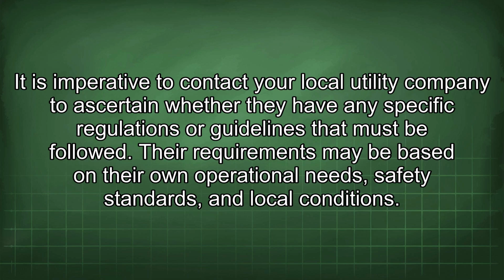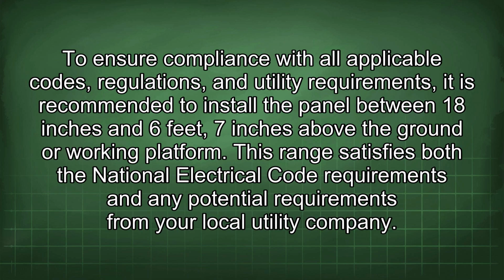It is imperative to contact your local utility company to ascertain whether they have any specific regulations or guidelines that must be followed. Their requirements may be based on their own operational needs, safety standards, and local conditions. To ensure compliance with all applicable codes, regulations, and utility requirements, it is recommended to install the panel between 18 inches and 6 feet 7 inches above the ground or working platform. This range satisfies both the National Electrical Code requirements and any potential requirements from your local utility company.